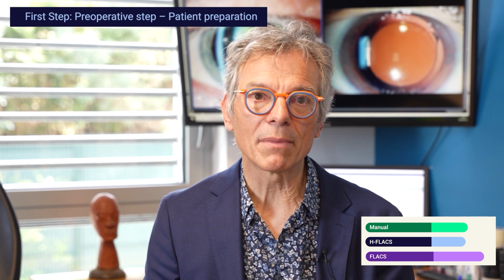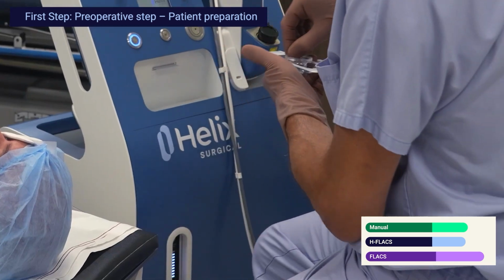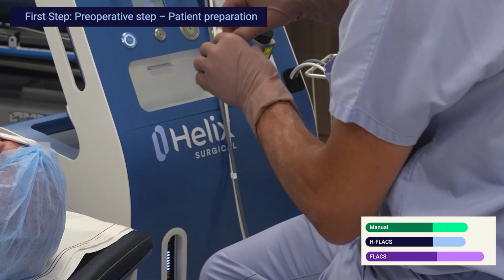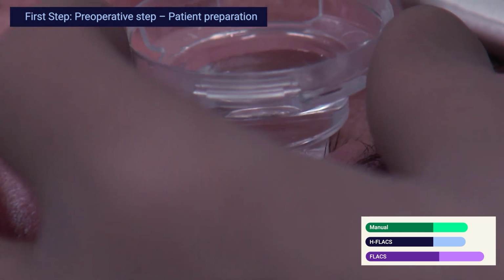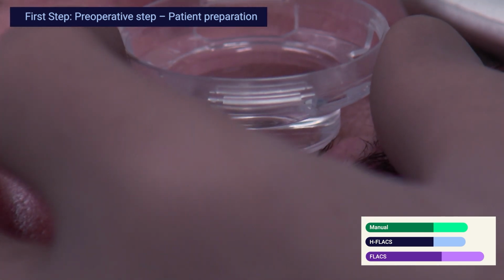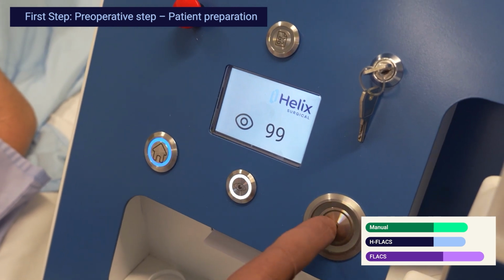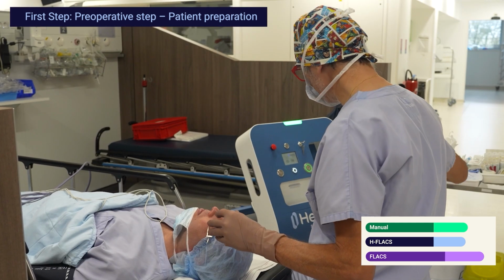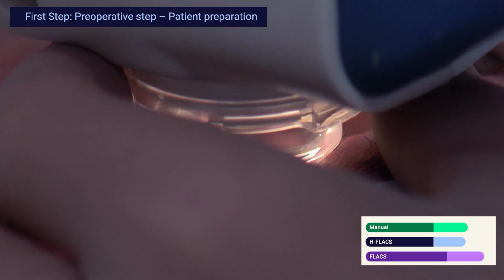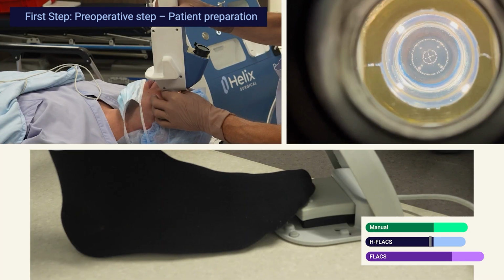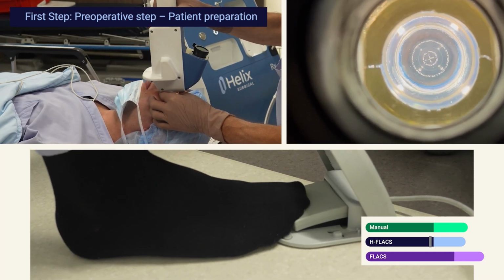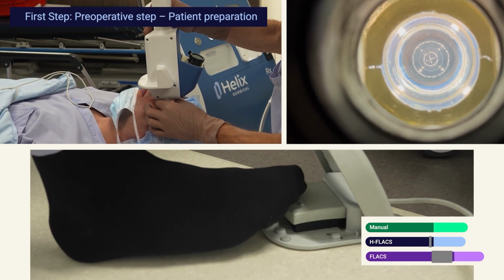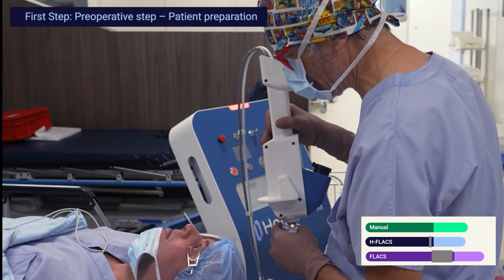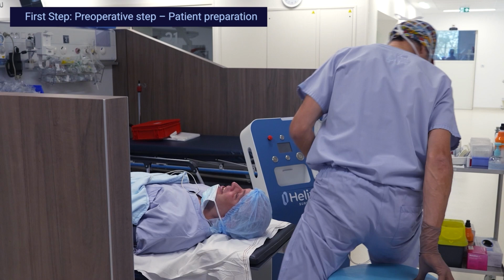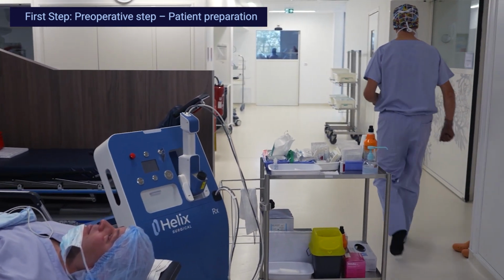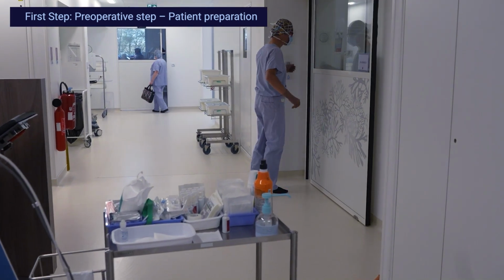The mobility of the battery-powered system allows me to easily position the laser near the patient. The absence of suction and settings allows me to place the interface directly on the eye, unlock the laser safety, grasp the handpiece and position the device while adjusting the centering. The laser shot, which lasts only 4 seconds, can then be triggered. In less than a minute, the capsulotomy is completed, and I can return to the operating room where the previous patient has already been set up. This organization optimizes my time, avoids an additional step in the operating room, making the transition smooth and perfectly integrated into the standard workflow.